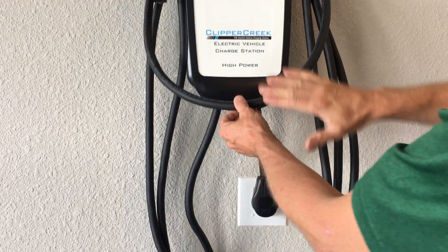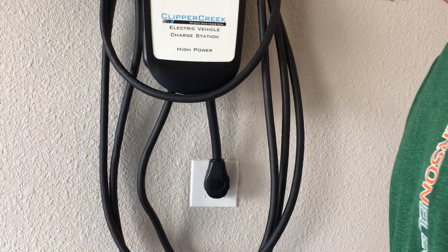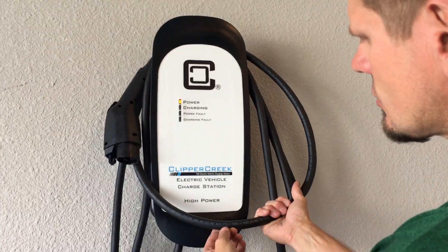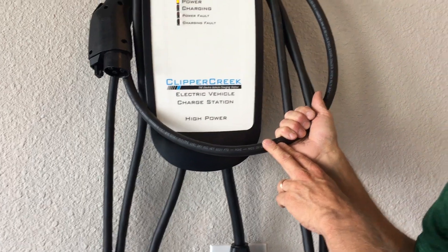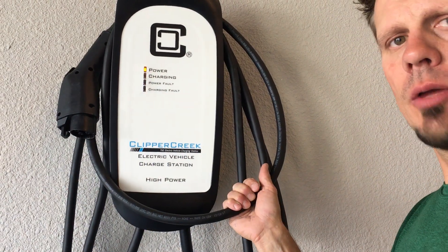This cord is rated with manufacturers, so it can literally be screwed on a wall and plugged in, like pulling a vacuum out of a box. You don't want to go trying to do this yourself — they are specially rated cords. It is 10-gauge. It is also a J-SOW — rated for wet and dry. It's also extra hard duty. So it's not something I would practice driving my car over, trying to save money. Keep in mind that where you place it matters.